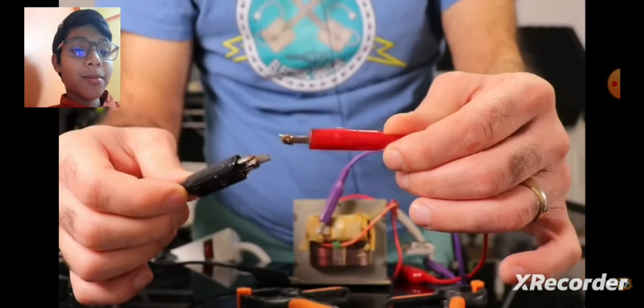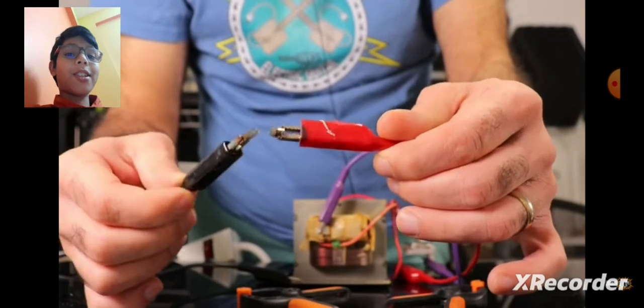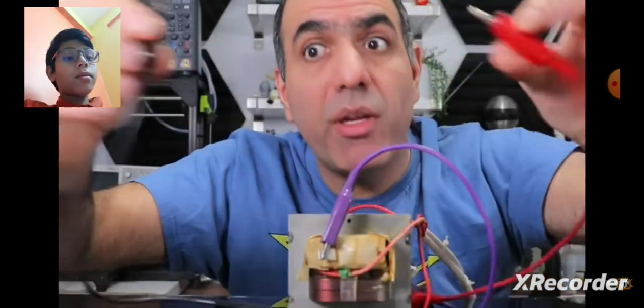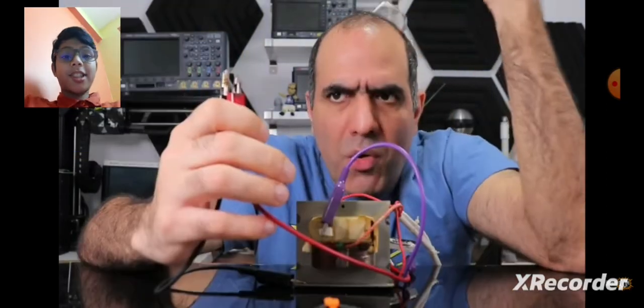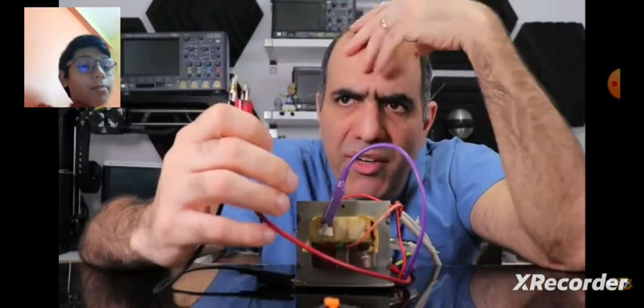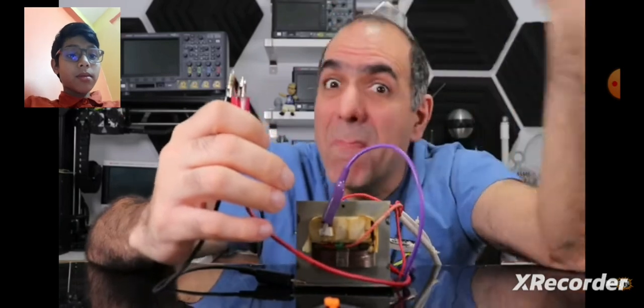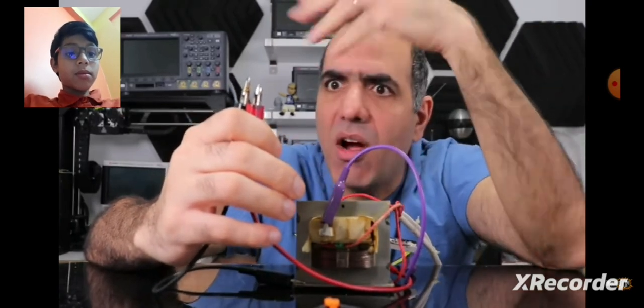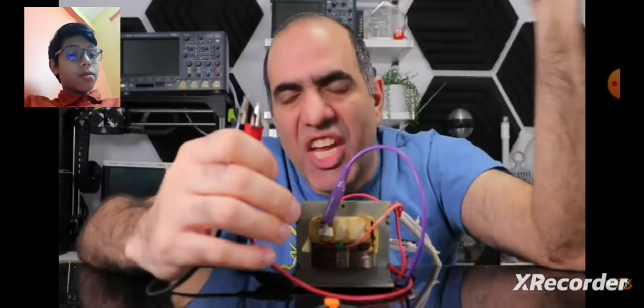Look at this, even the glass cracked and broke under extreme heat. The voltage rating is not about the normal operating mode, it's for when the fuse breaks open and we want it to reliably open. We know a strong high voltage can jump the gap, creating an arc, keeping the circuit closed, like we saw. So in order to make sure a fuse or breaker actually opens, it needs to be made differently. Otherwise the arcs never die, and that's not safe.